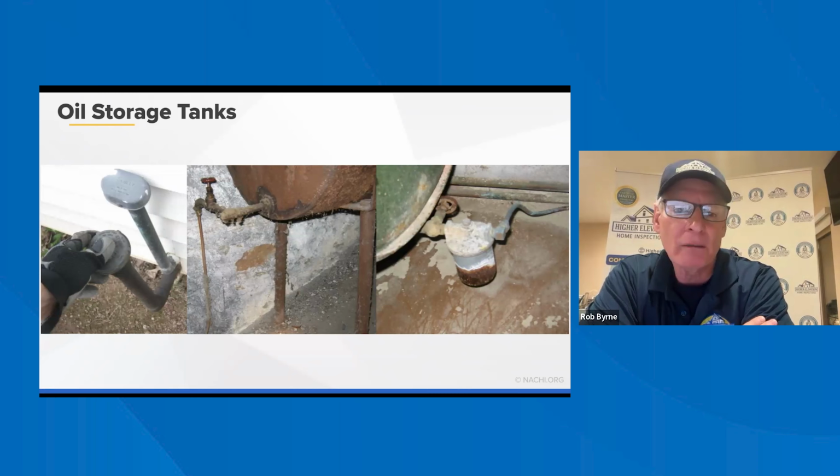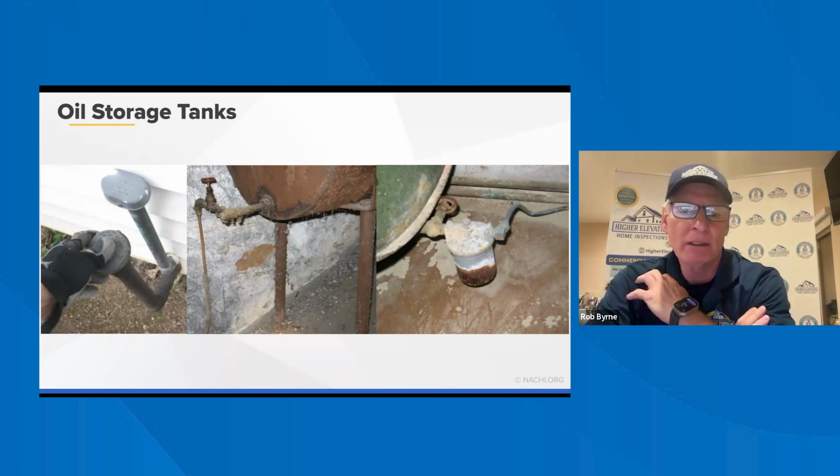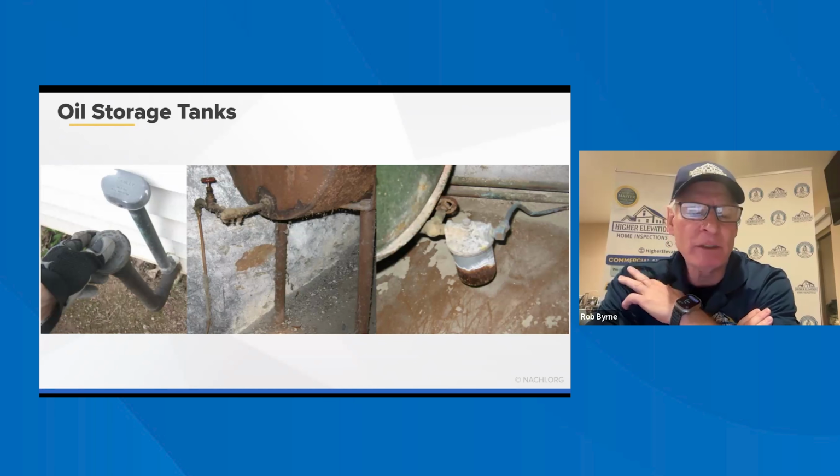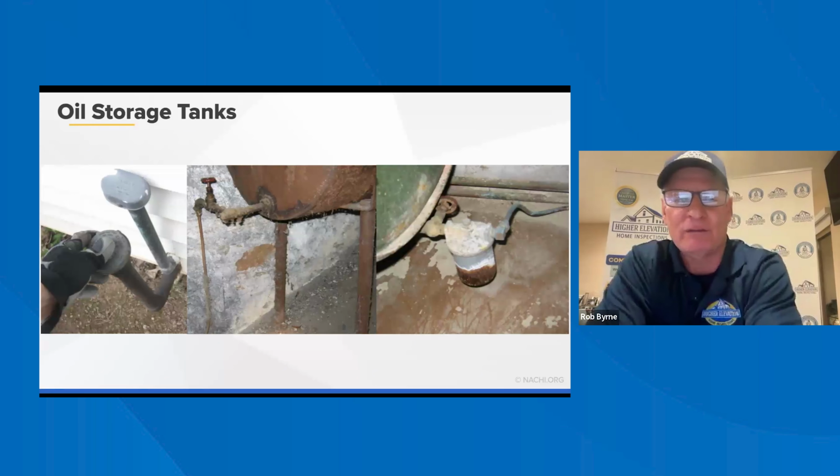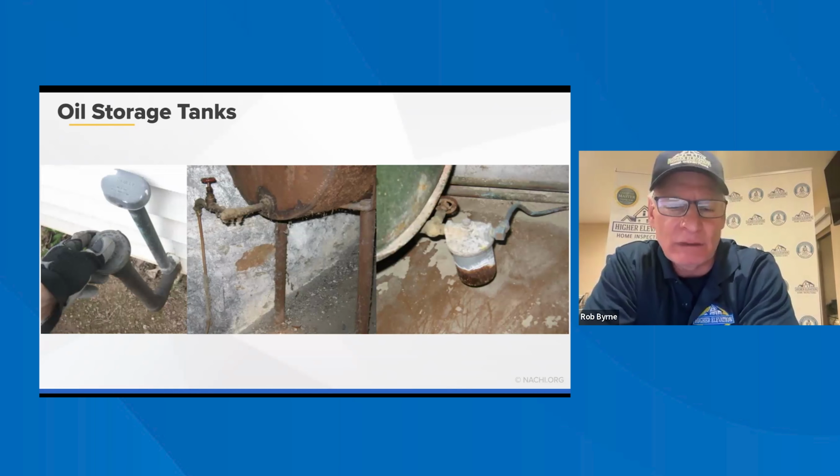It's not good. So as part of your inspection, knowing where the fuel storage tanks are located, up here in the Northeast, and again, if anybody's here in the South and Florida, any places like that, you're not really dealing with this. But in the Northeast, in New York, this is a major concern for us on inspections.